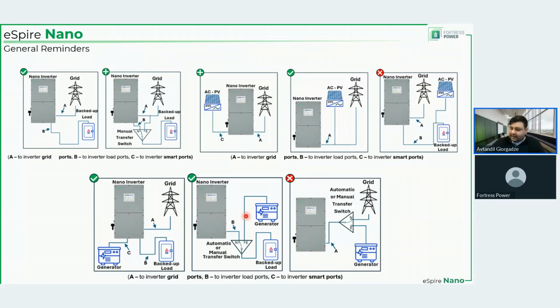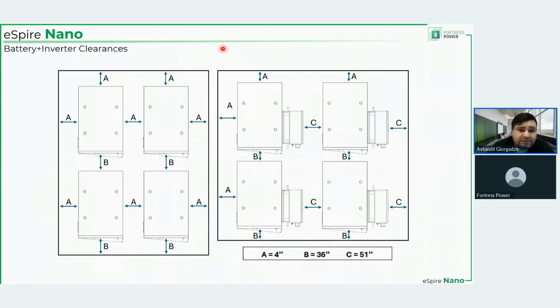But what you cannot do is have the automatic or manual transfer switch upstream of the inverter and the generator being able to provide power to the inverter grid ports. As I said before, grid ports are reserved for the grid, not the generator. Okay, so with this out of the way, let's get into the battery and inverter clearances, when you have batteries by themselves or when the inverters are mounted on the sides of the battery cabinets.